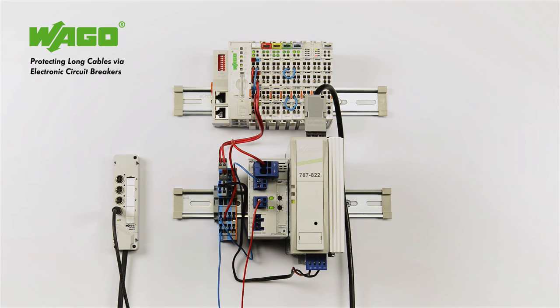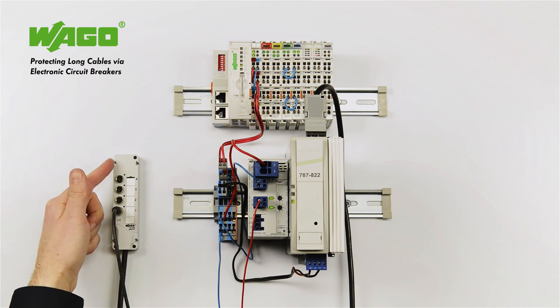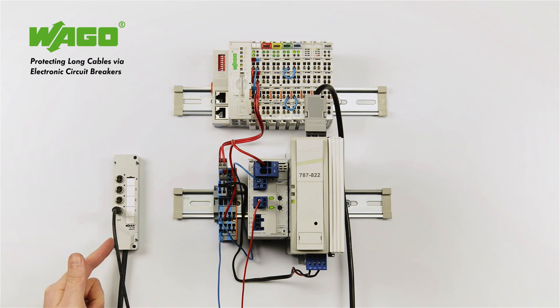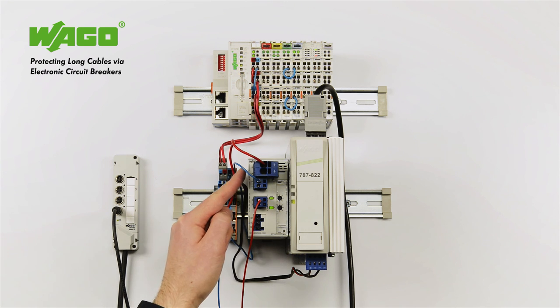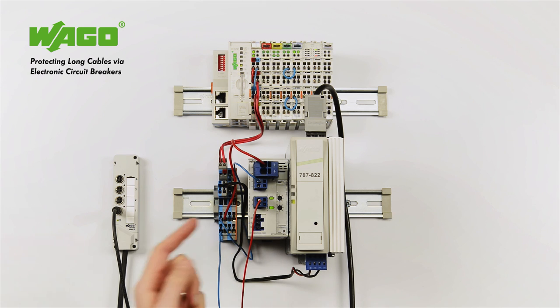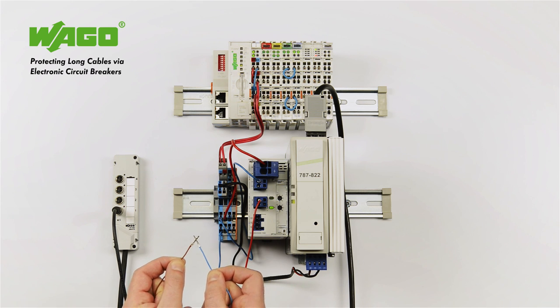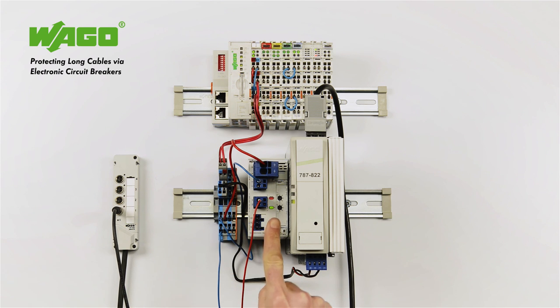In this setup, we have connected a 15-meter cable to the sensor actuator box. A sensor is connected to the box by an additional 3-meter cable. If reliable triggering of a miniature circuit breaker is prevented because the cable is too long, only an electronic fuse can remedy the situation. The fuse trips reliably in only a short time, as electronic fuses require a lower trip current than thermomagnetic circuit breakers. The red flashing LED indicates that a channel has been tripped.